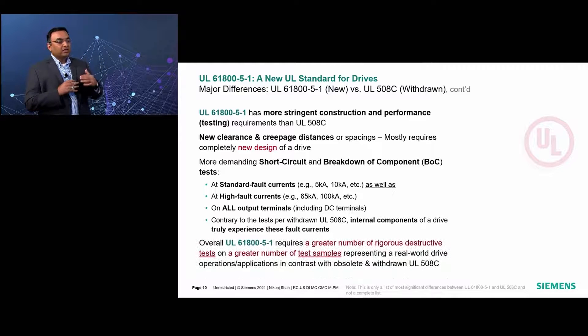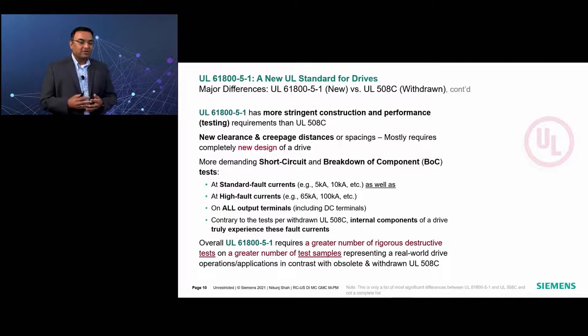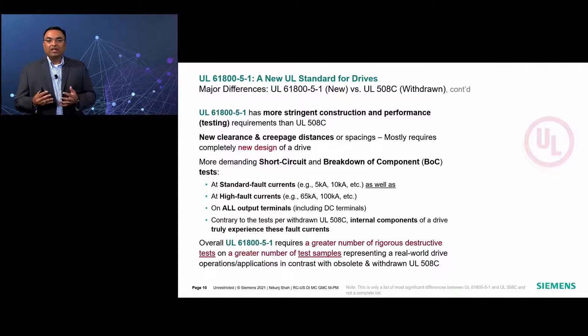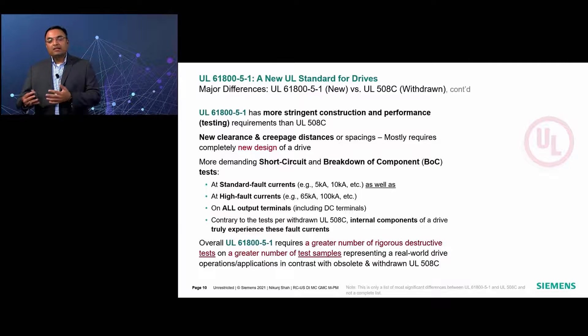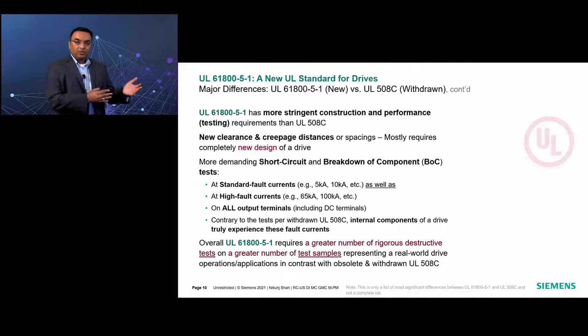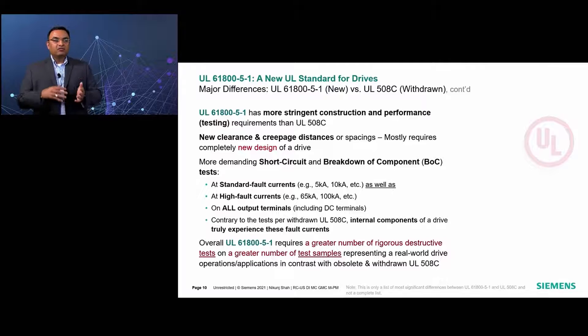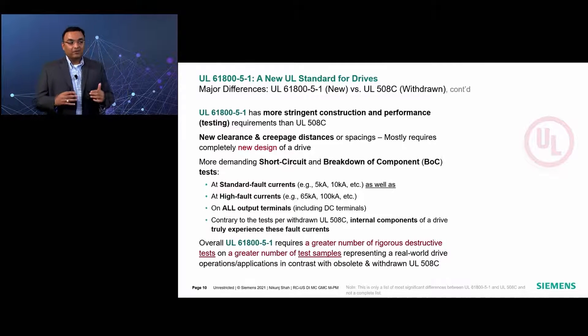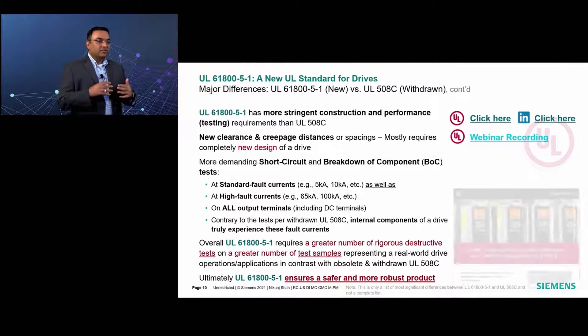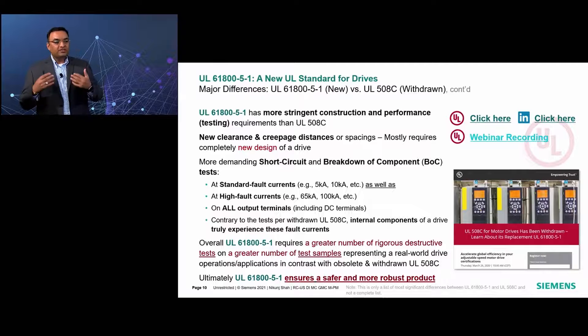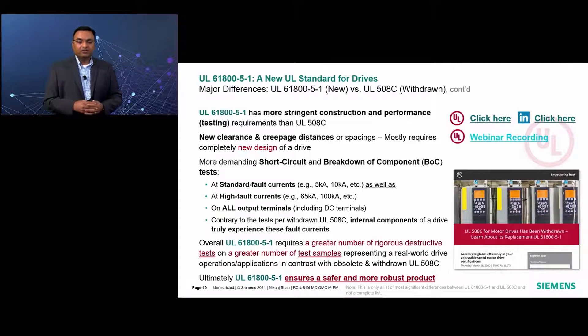Overall, 61800-5-1 requires a greater number of more rigorous destructive tests on a greater number of test samples, representing real-world drive operation and application conditions in comparison with the obsolete and withdrawn UL508C. This is to ensure the enhanced level of product safety — not only in normal operating conditions, but also in abnormal operating conditions as well as fault conditions — so the drive does not pose any kind of risk considering real-world application situations. Therefore, a drive with an inherently robust design and reliable components can pass such tests, and the drive under UL61800-5-1 ensures a safer and more robust product compared to drives certified according to UL508C.